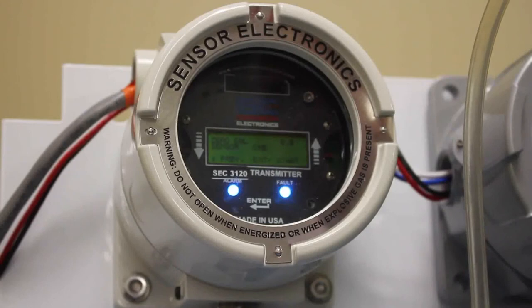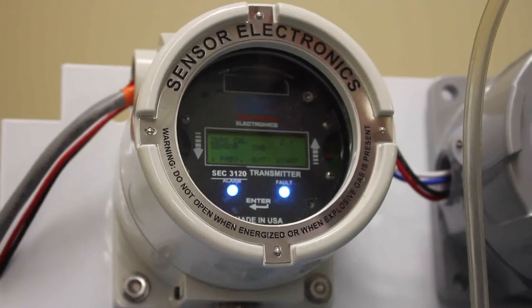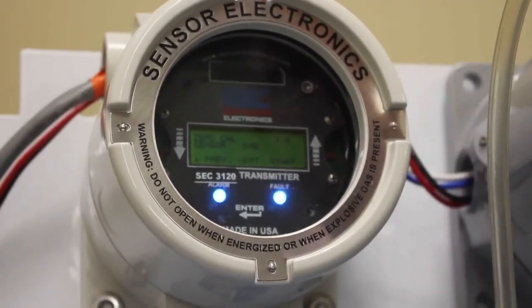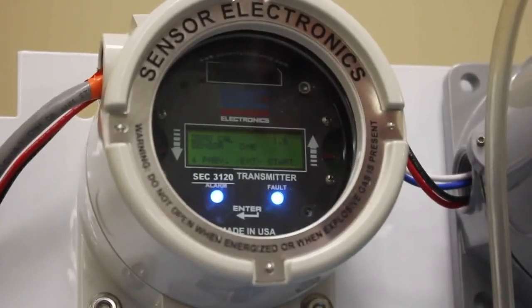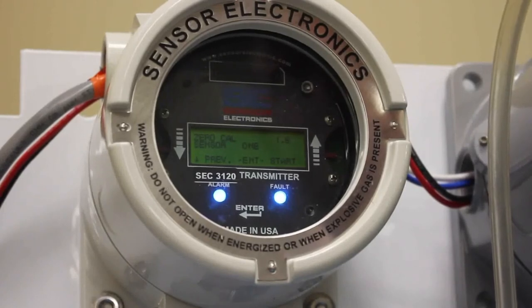So what you'll do is you'll just apply the nitrogen, let it flow. Typically we're using a liter per minute flow regulator to apply the nitrogen gas to it. And once the sensor reading remains stable, hopefully somewhere around 0%, then we would actually zero calibrate the sensor. As you can see, it's still slowly moving down. So it looks pretty steady. It's reading 1.5, 1.6. So I'll just go ahead and zero the sensor.